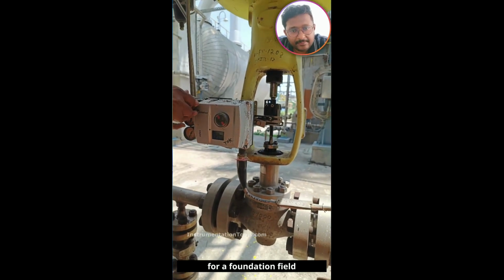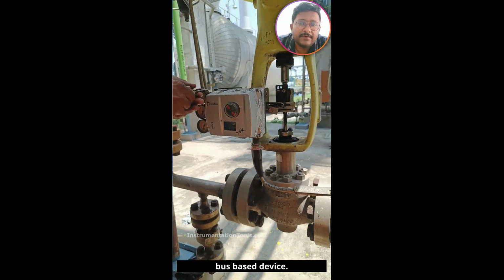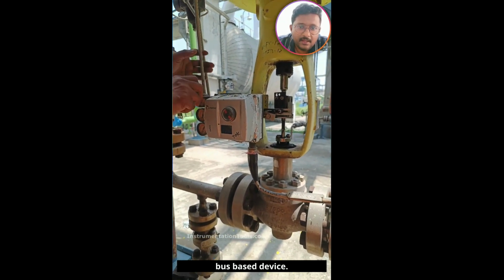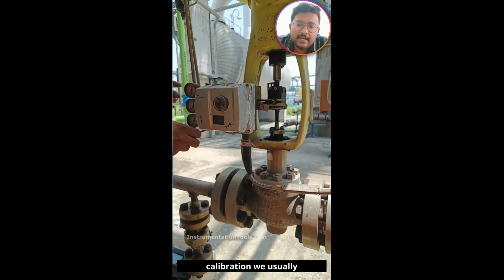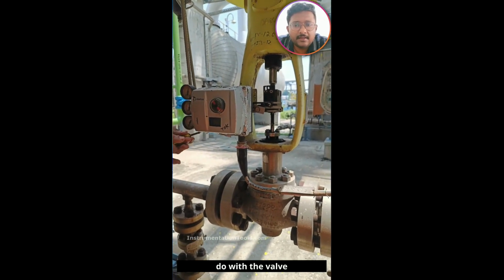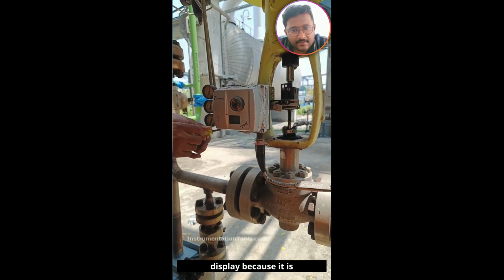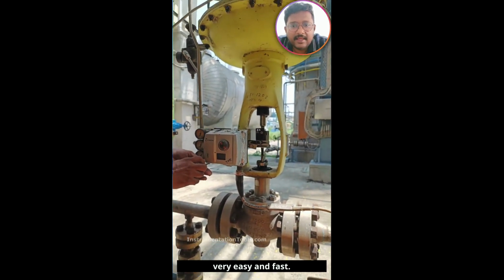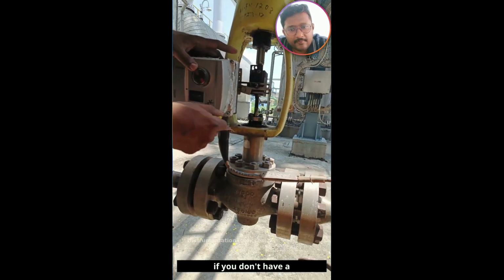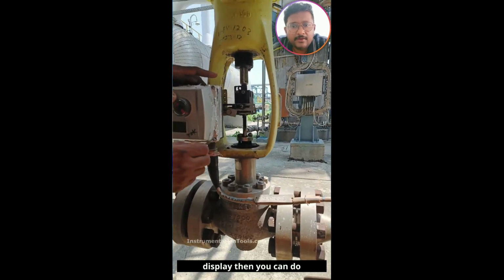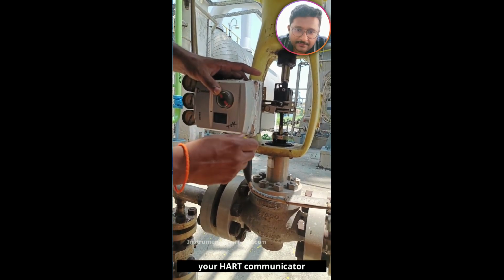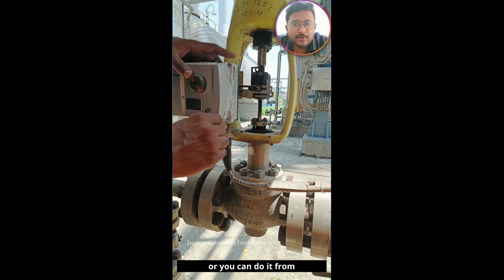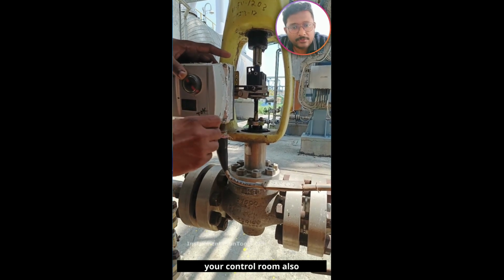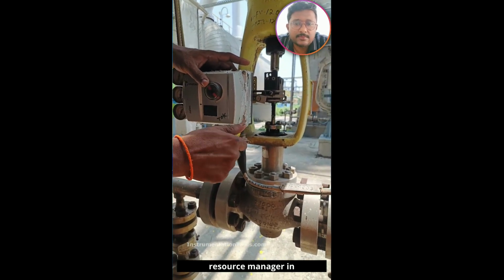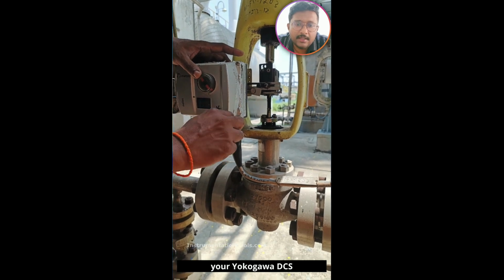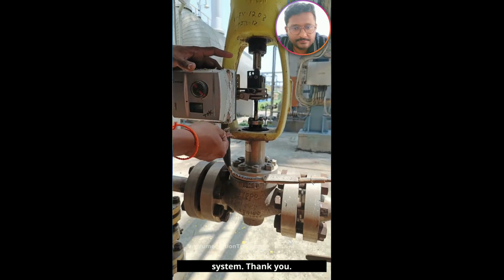Remember, it takes time for a foundation field bus based device. For doing the control valve calibration, we usually do with the valve display because it is very easy and fast. If you don't have a display, then you can do it with your HART communicator or you can do it from your control room also if you have a plant resource manager in your Yokogawa DCS system.